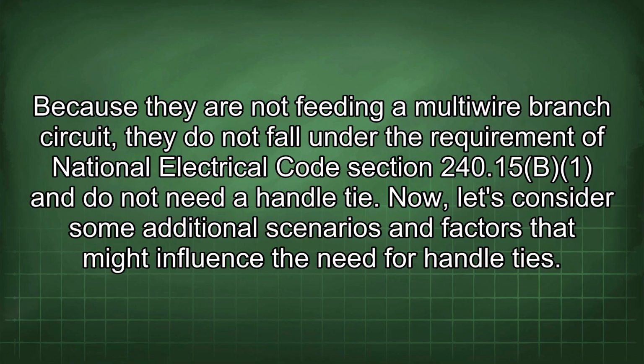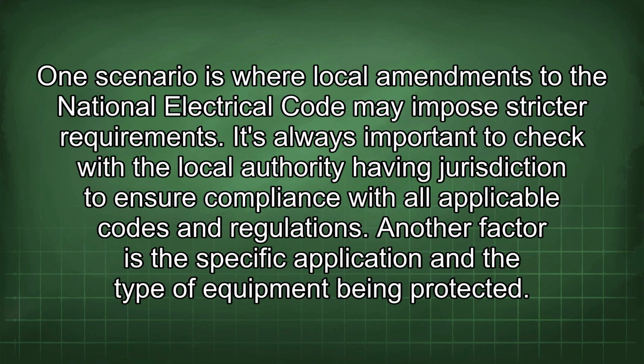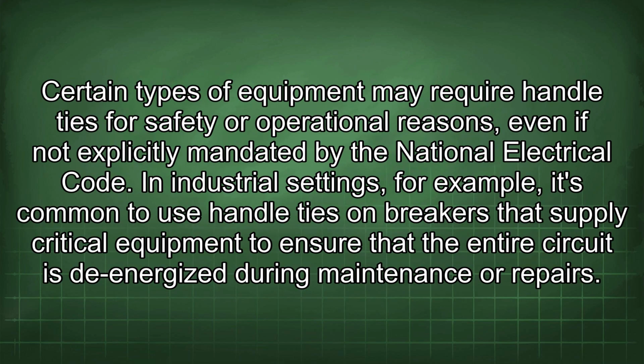Now, let's consider some additional scenarios and factors that might influence the need for handle ties. One scenario is where local amendments to the National Electrical Code may impose stricter requirements. It's always important to check with the local authority having jurisdiction to ensure compliance with all applicable codes and regulations. Another factor is the specific application and the type of equipment being protected. Certain types of equipment may require handle ties for safety or operational reasons, even if not explicitly mandated by the National Electrical Code. In industrial settings, for example, it's common to use handle ties on breakers that supply critical equipment to ensure that the entire circuit is de-energized during maintenance or repairs.